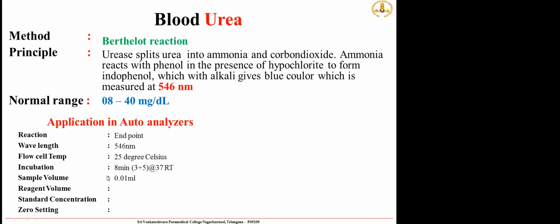Okay, and here the sample volume is 0.01 ml, and the reagent volume is 1 ml, and the standard concentration is 20 milligram per dl. And inside this auto analyzer we have to keep the zero setting with the help of reagent blank.